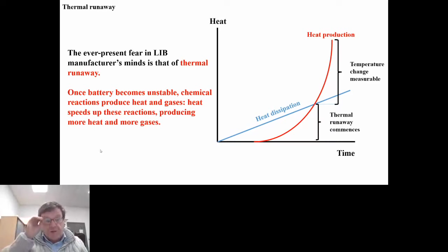Now, when thermal runaway takes place and prior to ignition, the gases will vent, and when they vent, they produce a thick white vapor. This white vapor can be mistaken for smoke, or even steam. It's white because it takes with it droplets of the organic solvents. Typically it contains up to 30 to 50% hydrogen, a large amount of carbon monoxide, carbon dioxide, hydrogen fluoride, hydrogen chloride, and hydrogen cyanide, all of which are pretty nasty, and small amounts, up to about 10%, of methane and other hydrocarbons. In other words, it's a vapor cloud.